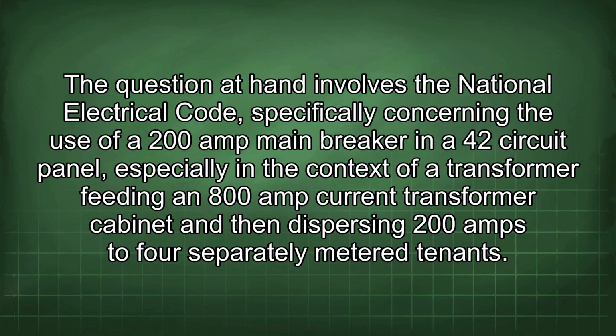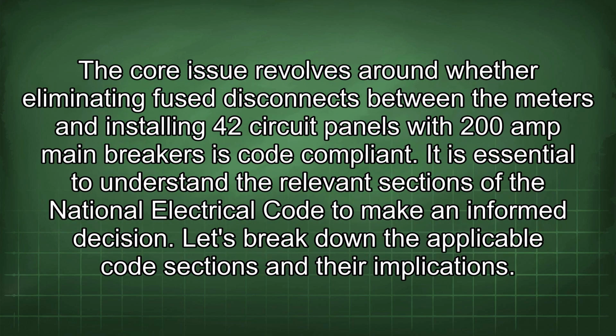The question at hand involves the National Electrical Code, specifically concerning the use of a 200 amp main breaker in a 42 circuit panel, especially in the context of a transformer feeding an 800 amp current transformer cabinet and then dispersing 200 amps to 4 separately metered tenants. The core issue revolves around whether eliminating fuse disconnects between the meters and installing 42 circuit panels with 200 amp main breakers is code compliant.